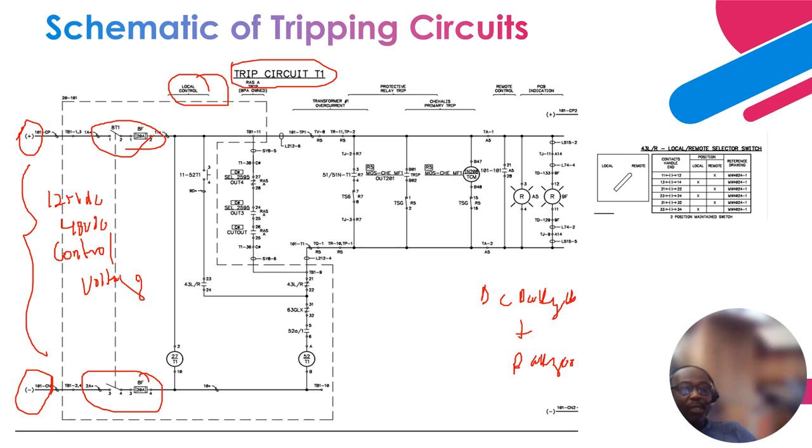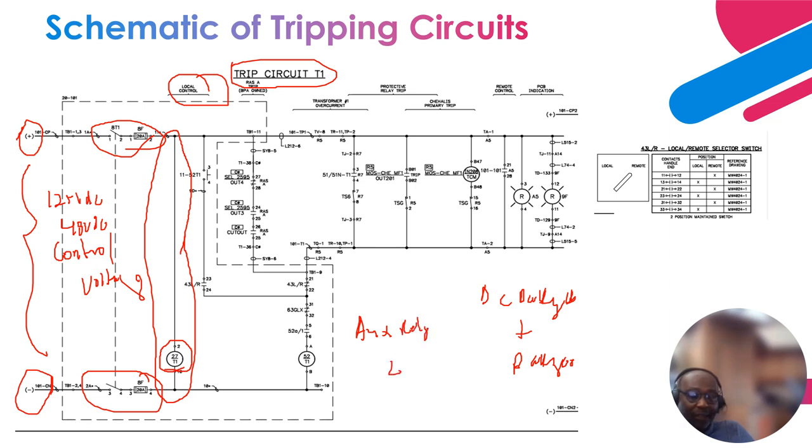As you know, that is spelled out. And similarly, just like the closing circuit, where I mentioned there is something called the permissive string, all the series of contacts, all the series of functions that are required to be able to trip the circuit are needed. Okay, so the first one is the under voltage condition, right? That auxiliary relay, 27, means under voltage. That control relay has to be energized. The coil of that has to be energized, so it is always energized. Let me put it that way.